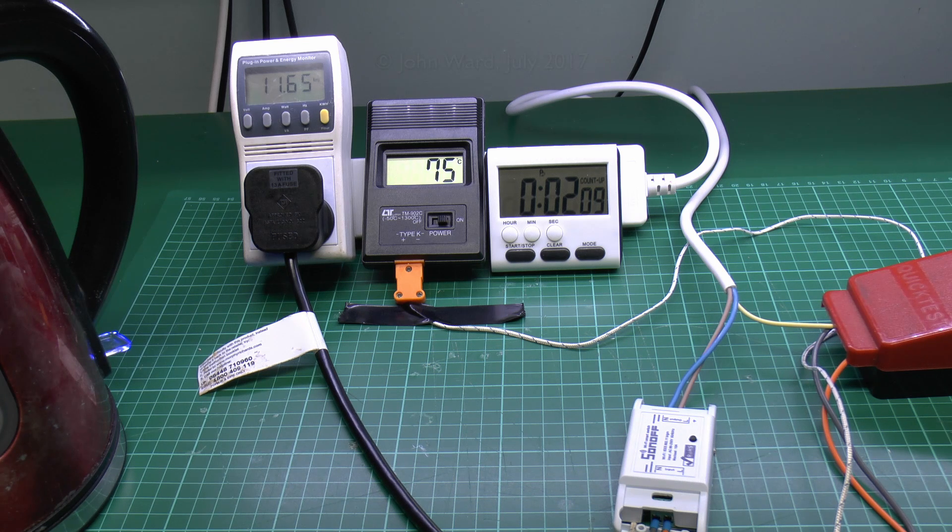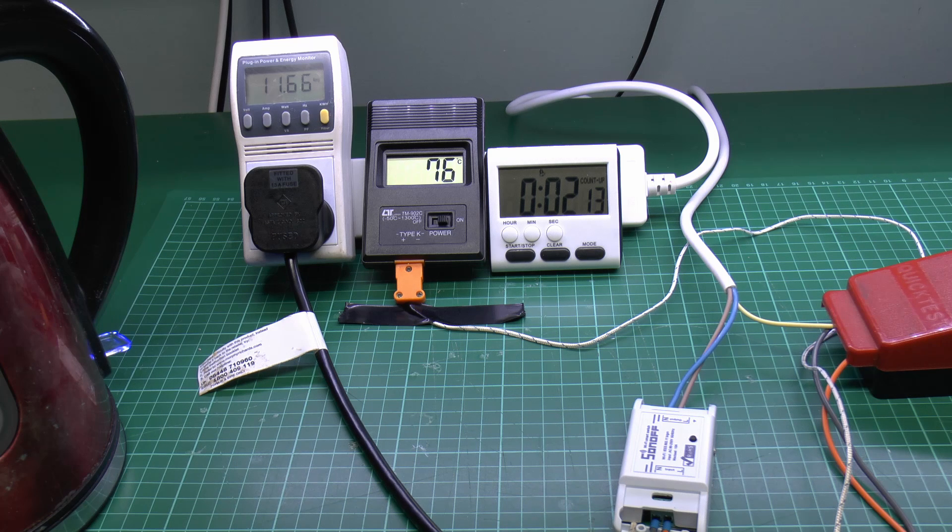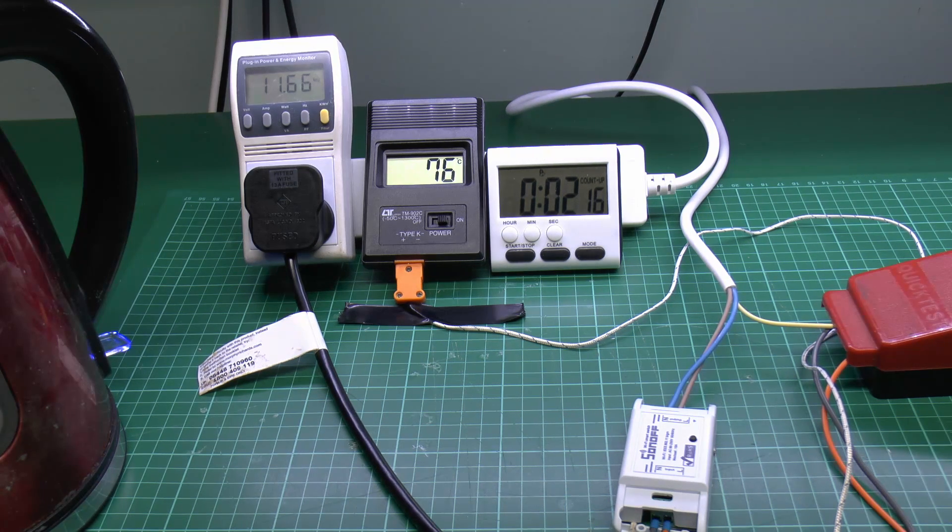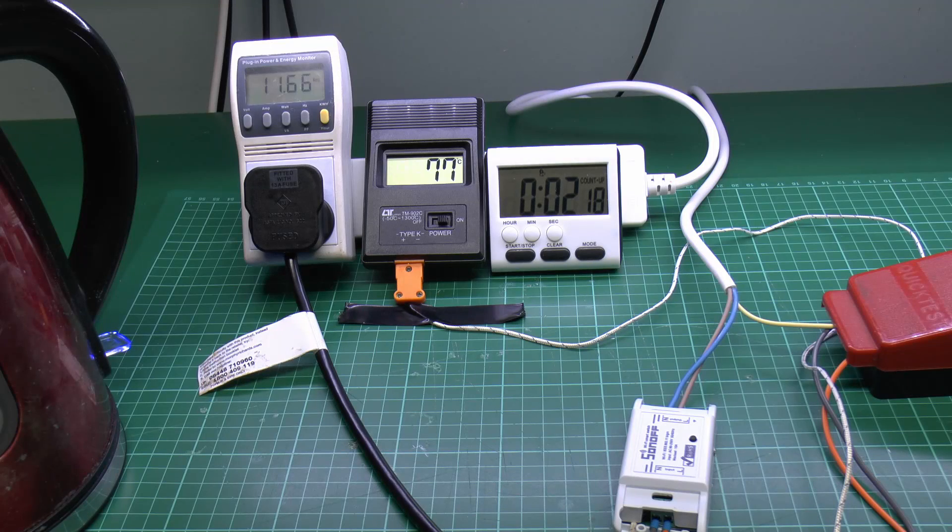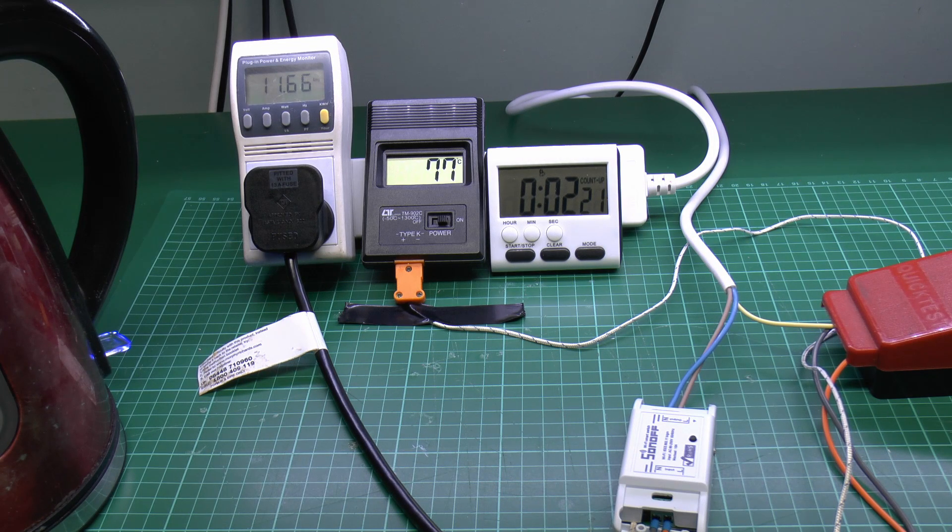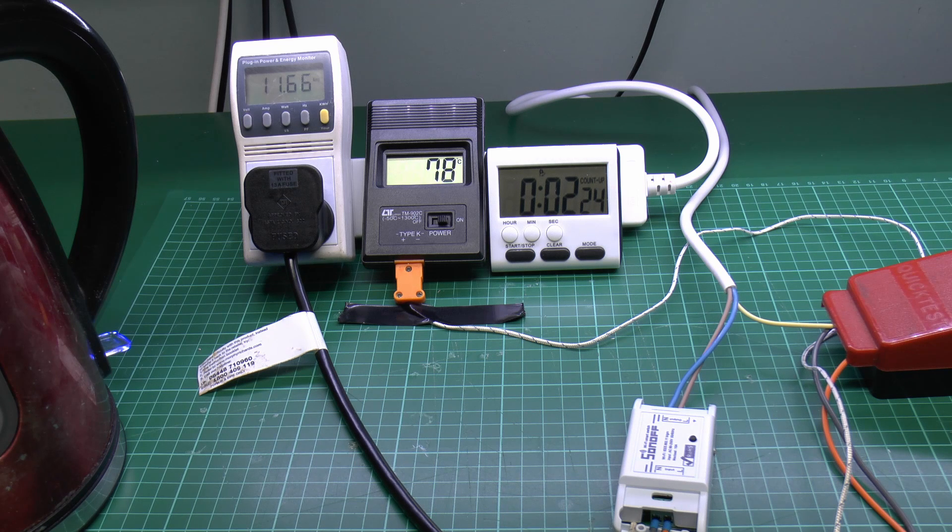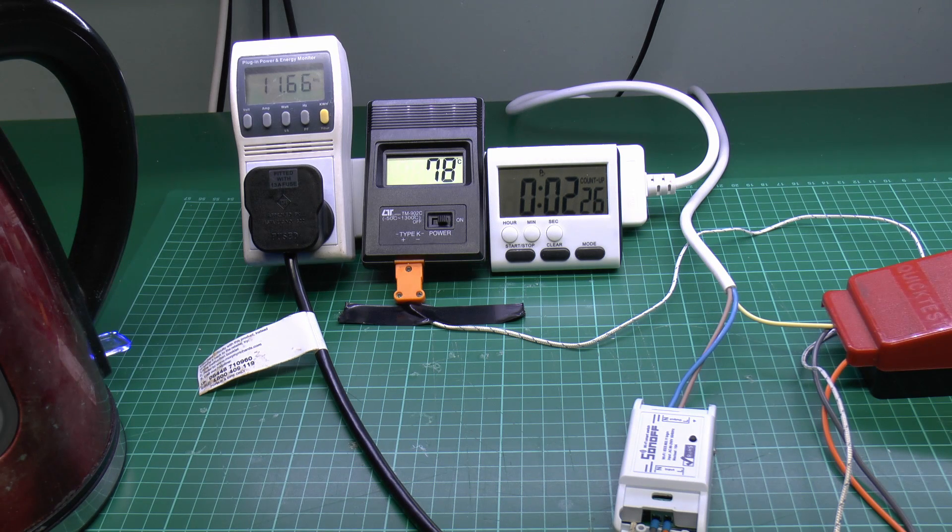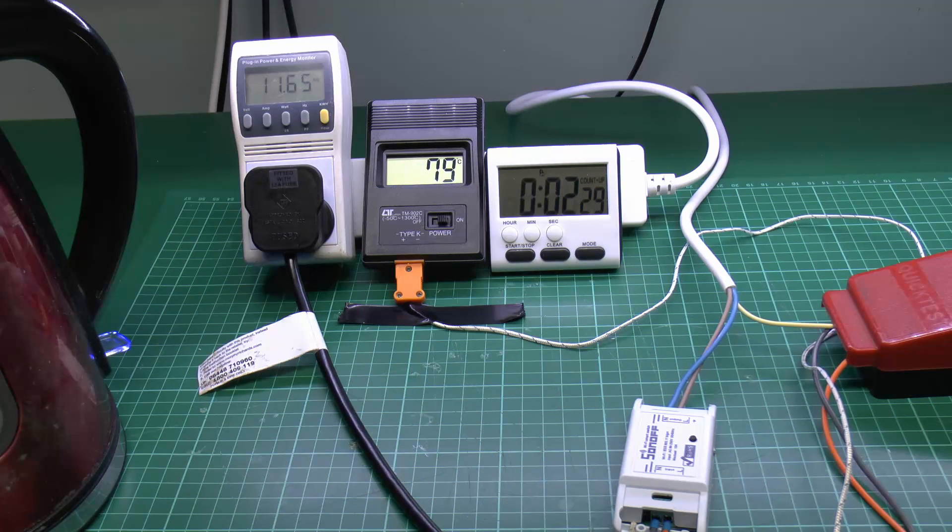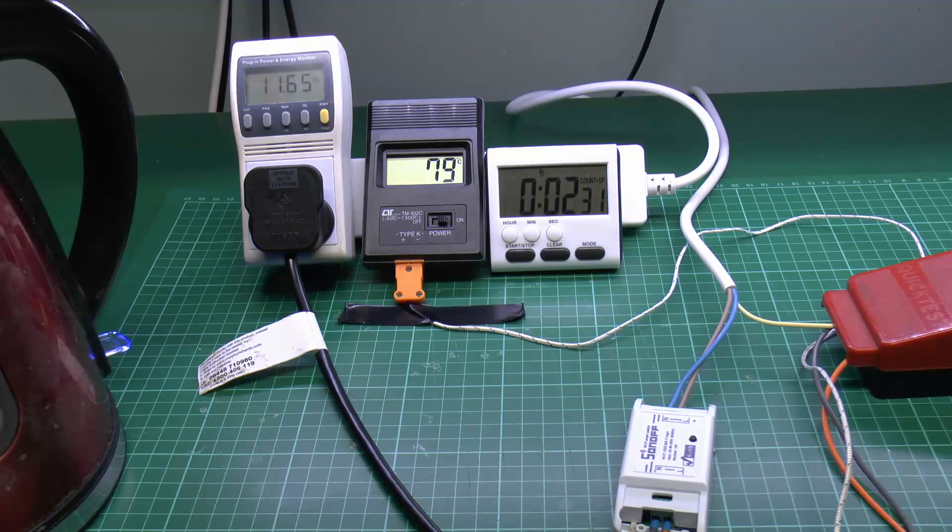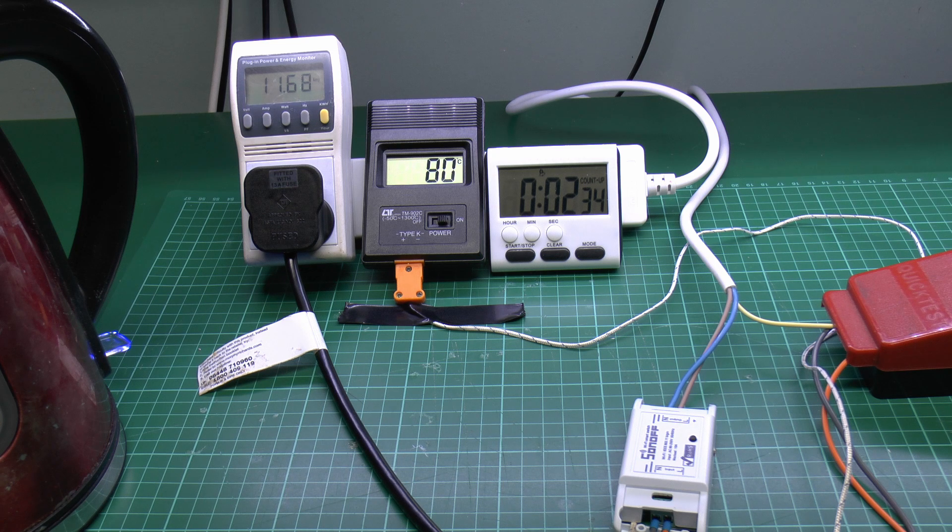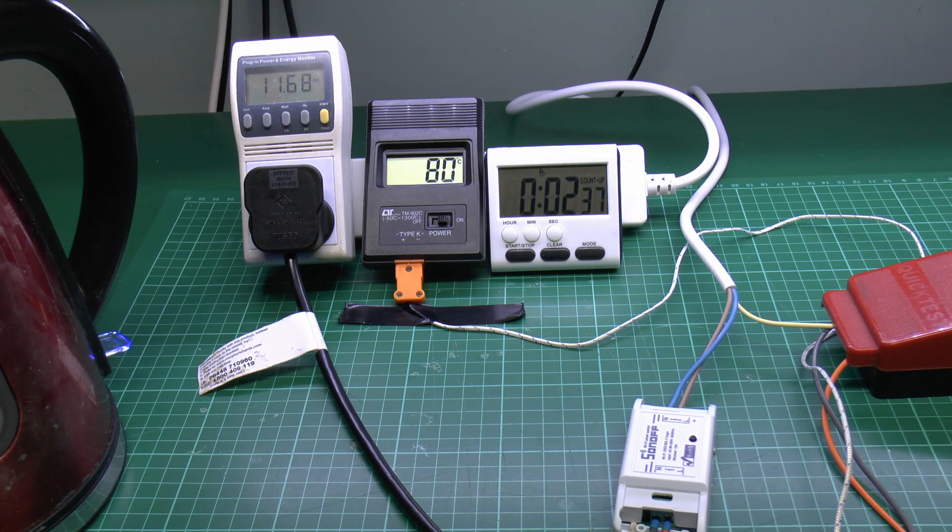So about 2 minutes 10 seconds in, and temperature is about 76 centigrade there. So it's certainly at the higher end of where you would expect conductors to get to. But being this is actually an overload, you would expect it to get a bit hotter than normal. But it's not going out of control or melting or setting on fire or anything, so that seems perfectly acceptable. Now it's coming up to the actual boiling point here, so we'll just let that complete and see where it gets to in the end.